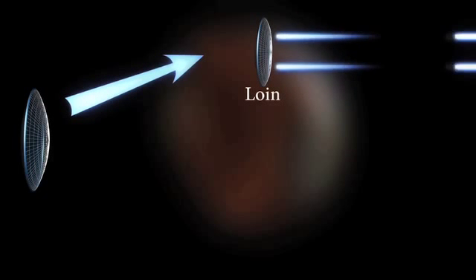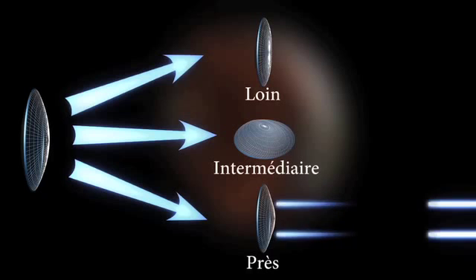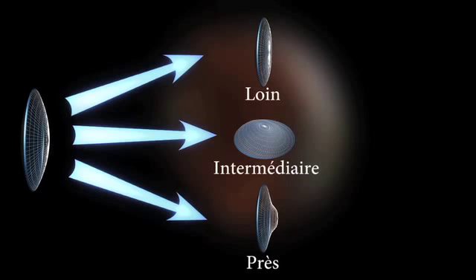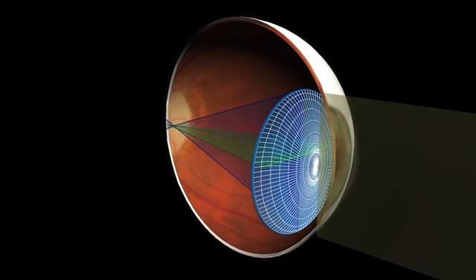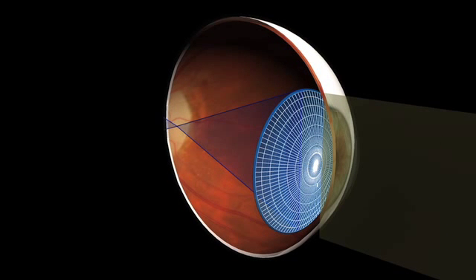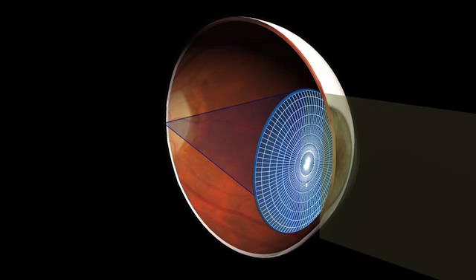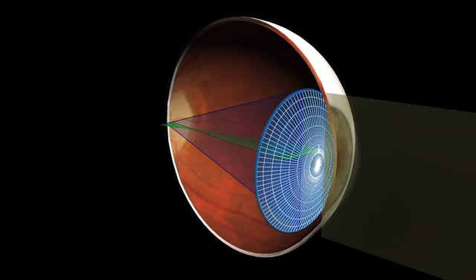Until the lens is locked, the patient needs to wear protective goggles to avoid changes induced by ambient light. To correct presbyopia, the procedure must include a primary correction for distance vision, followed by the modulation of asphericity to compensate for intermediate vision, or the making of an addition zone centered on the lens. Residual astigmatism after cataract surgery can be corrected at the same time. The balance between distance and near vision can be tuned during the adjustment procedures after surgery, depending on the pupil size and the requirements of the patient. At the end of the procedure, both distance and near vision are available to the patient.